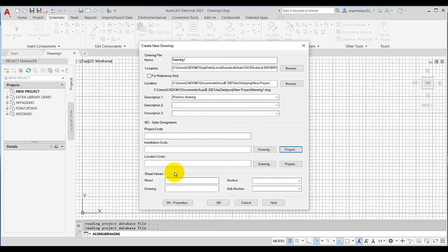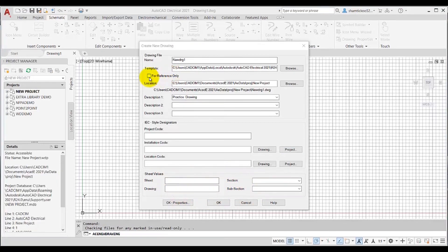In the Sheet Values area, you need to enter the values for the sheet, drawing section, and subsection in the edit boxes. Now let us discuss the For Reference Only checkbox. This checkbox is used to create reference drawings, which are used for cover sheets, terminal plans, and other non-electrical layouts in a project. These drawings save processing time for AutoCAD Electrical functions. Note that reference drawings will be included in project-wide plotting and title block update operations, but all other electrical smart functions such as cross-referencing, automatic tagging, and reporting will be non-functional for these drawings.